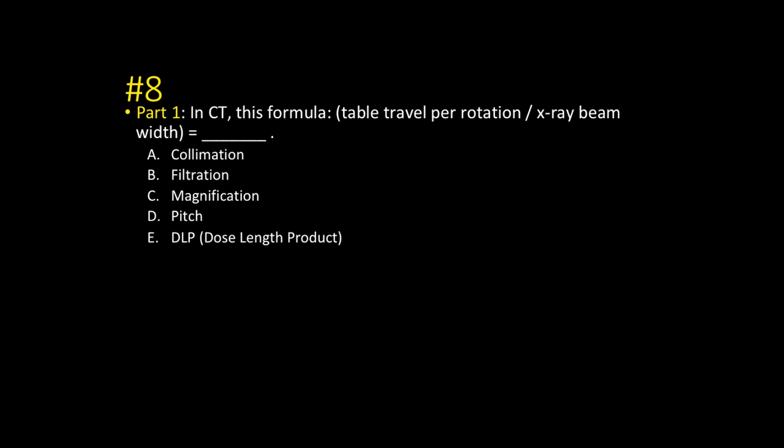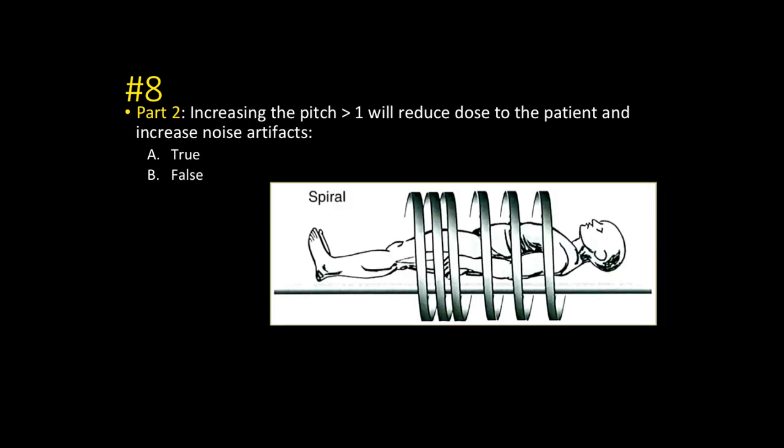Number eight — a physics question, not an artifact. In CT, the formula for pitch is: table travel per rotation divided by x-ray beam width. Part two: increasing the pitch greater than one will reduce the dose to the patient but increase noise artifacts. You're increasing the space between acquisitions, which reduces dose but gives you a worse image with more noise.